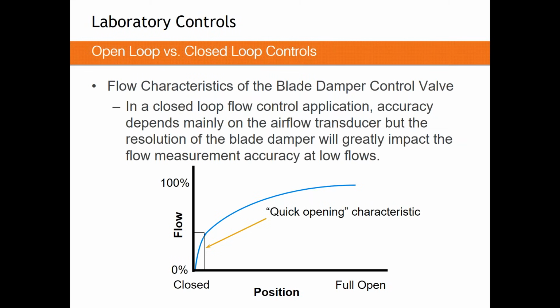That's why we like to get them into that much more linear opening area. Basically 25 to about 75% open, and that's highly dependent on your system, highly dependent on the box type and shape and size. But you basically want to be in that middle range to give you more linear, better, more accurate control.